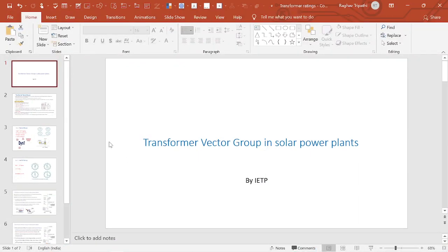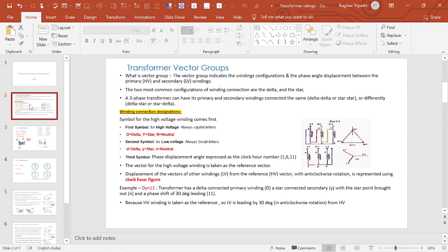Let us first discuss the basic concept of the vector group and winding configurations. The vector group indicates the winding configurations of HV and LV and the phase angle displacement between HV and LV. The two most common configurations of winding connections are delta and star.